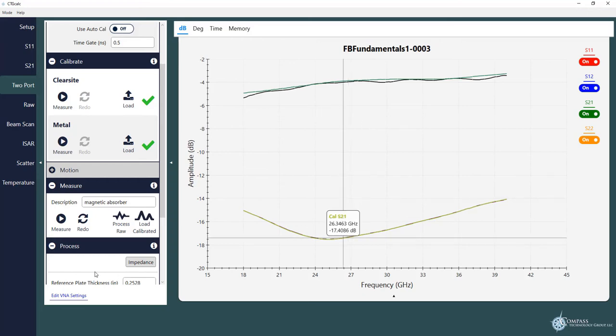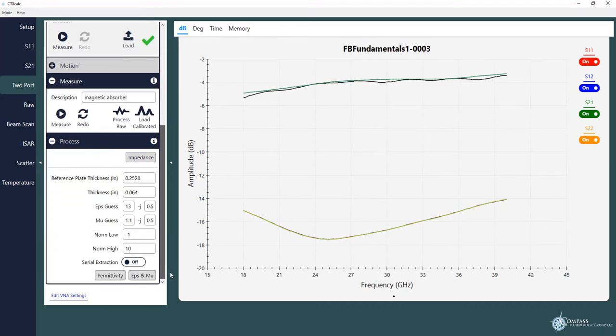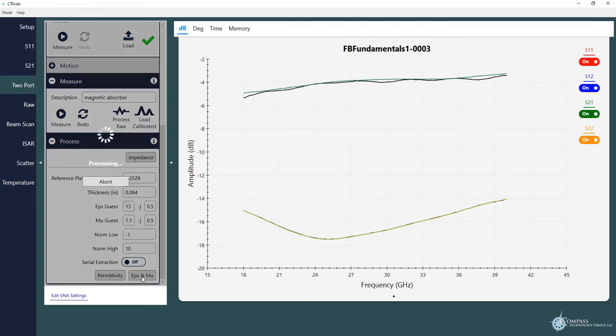And with that we can then do some additional processing to calculate our permittivity and permeability or epsilon and mu. So we've put in the thickness of our calibration plate. We put in the thickness of our specimen. We've given some initial guess values for the algorithm to search over. And then we just click the button and we let it do its thing.